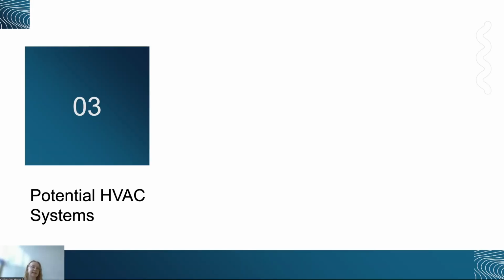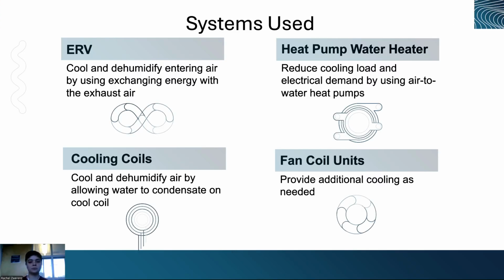For potential HVAC systems, we wanted to use an ERV to both cool and dehumidify the entering air, without using any electricity, just by using the exchange with the exhaust air. We also wanted to use cooling coils to cool and dehumidify the air, and then also use fan coil units to just provide additional cooling as needed. Something interesting is that we wanted to use a heat pump water heater in each of the units, as this is going to both reduce the cooling load in the unit and supply the hot water needed for the unit. So sort of a double whammy there as far as reducing the electricity we need.